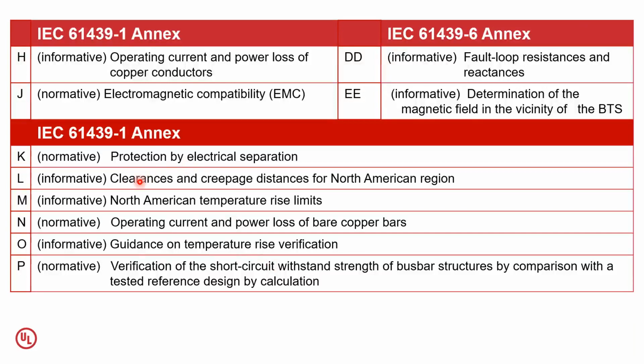So this annex provides some of the clearance and creepage distances that are required for any product that is supposed to be used in the North American region. This does not mean the product will be suitable for North America, but it is a slow and steady first step to start including the requirements of other regions so that the end user and the manufacturer also get a fair idea of what those differences are in the North American context. So all of them are informative, because this particular standard, IEC 61439-6, cannot be used in North America, because there are separate product standards for North America.